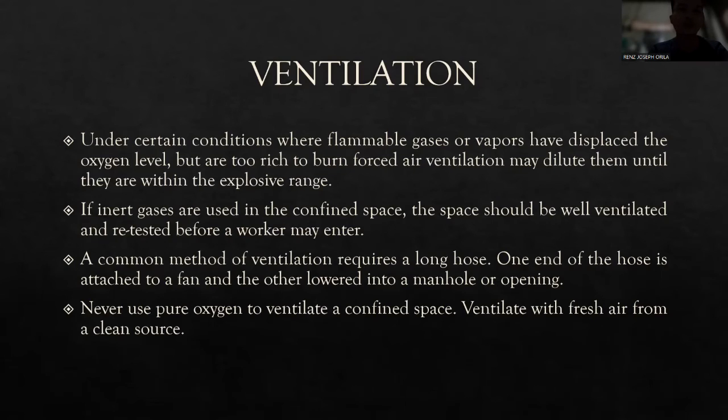Never use pure oxygen to ventilate a confined space. Ventilate with fresh air from a clean source because oxygen enrichment in enclosed areas increases the risk of ignition. An oxygen-enriched atmosphere above 21% will cause flammable materials such as clothing and hair to burn violently when ignited. And FYI, oxygen is not flammable, but it can cause other materials that burn to ignite.